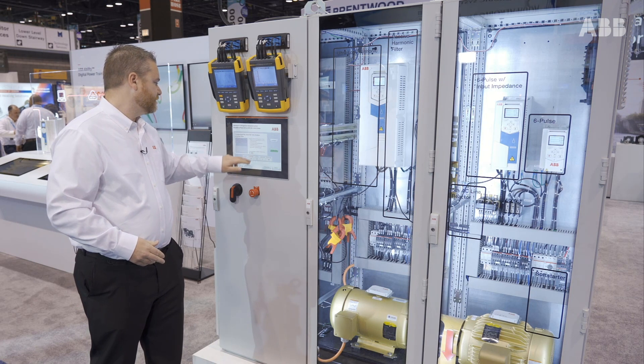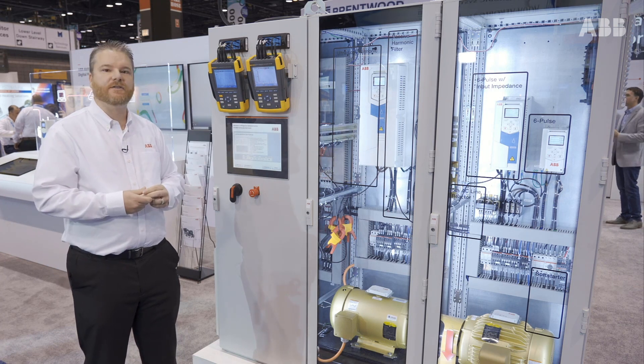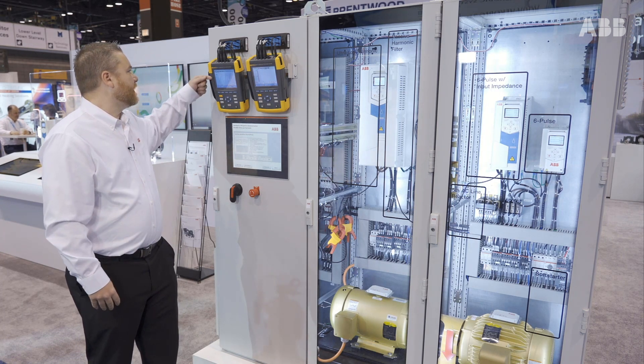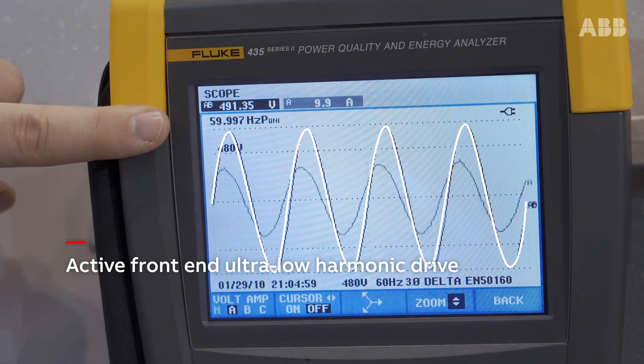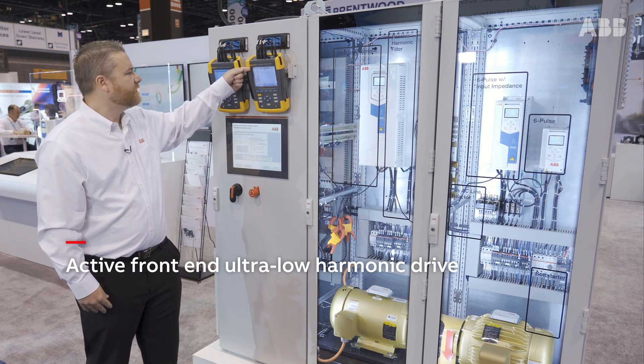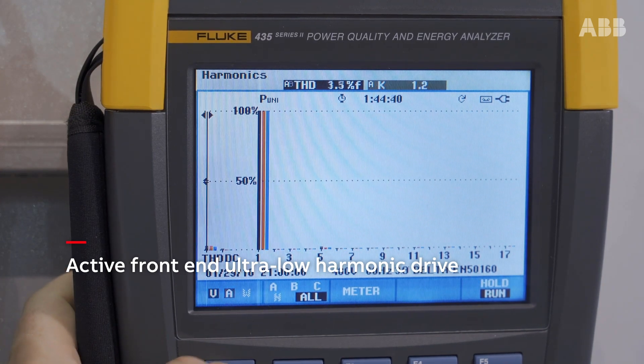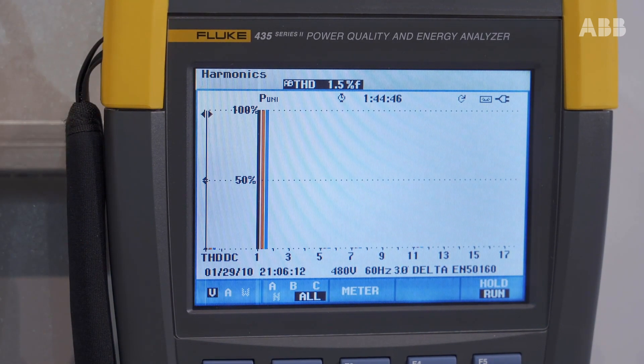Now I'm going to show the last drive — the ultra-low harmonic drive. This is an active front-end drive, so instead of using diodes, it has IGBTs on the front end. Looking at the scope image, that voltage waveform has no flat-topping at all. The current waveform is very, very sinusoidal. Looking at the measurement, your current distortion is 3% or lower — significantly better even than the passive filter. Voltage distortion is at 1.4%, which at this point is just background distortion from this facility's power source.